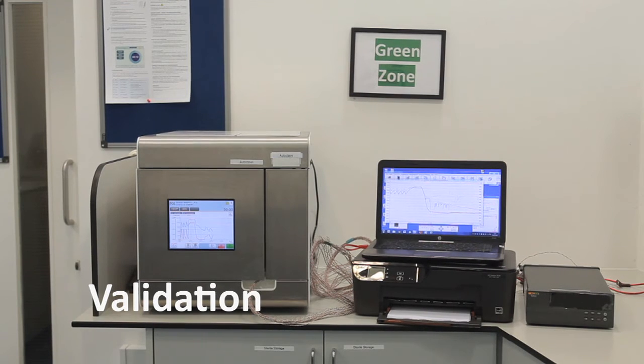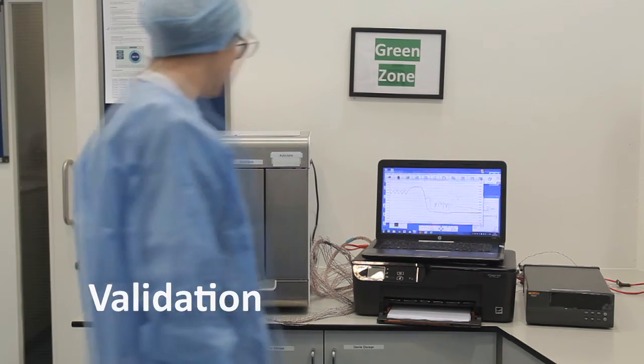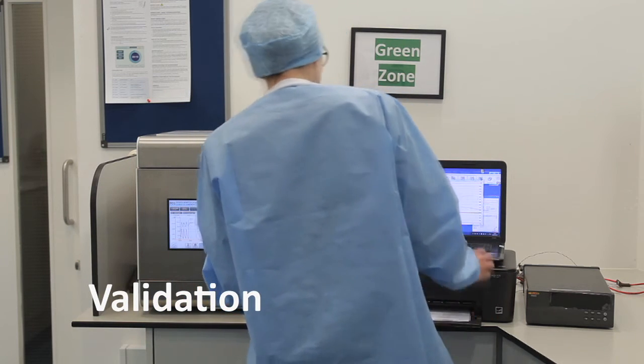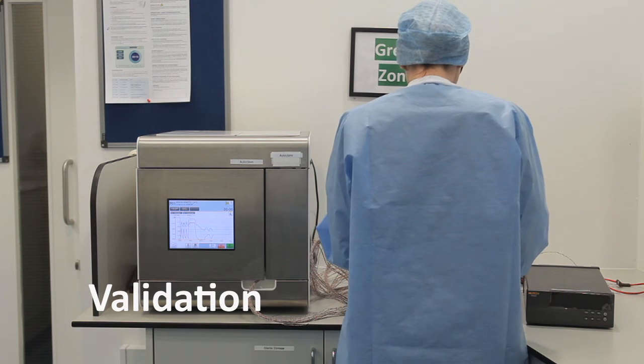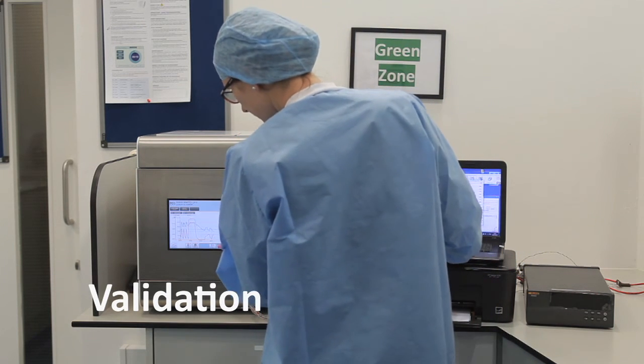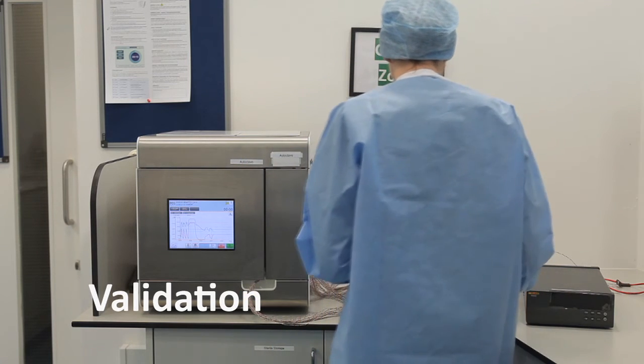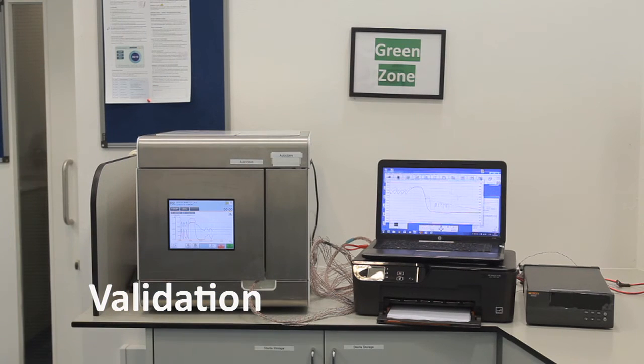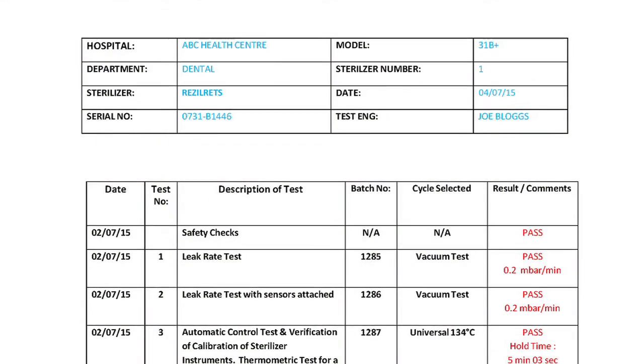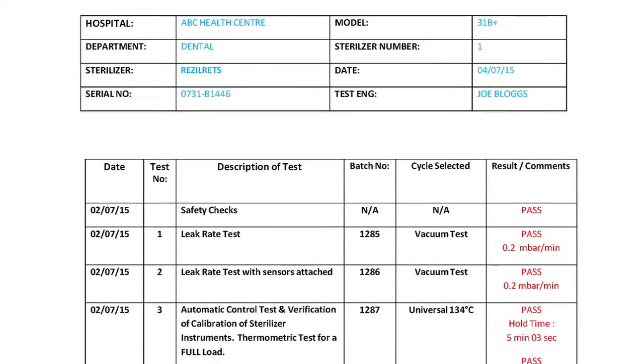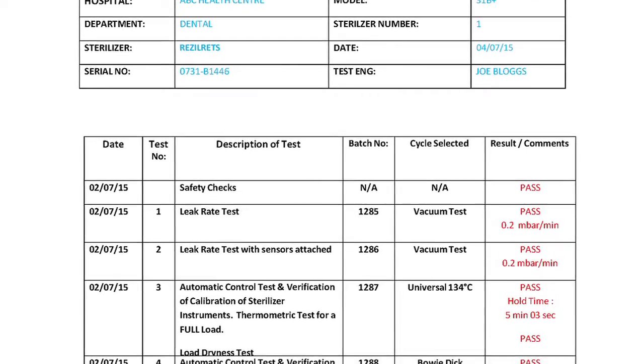Validation is the documented procedure for obtaining, recording and interpreting the results needed to show that a process will consistently yield a product complying with predetermined specifications. The process of validation is to examine all aspects of the decontamination and sterilisation process to determine if they are operating and functioning correctly. An independent engineer test person from an outside organisation is required to service, repair and validate the ultrasonic bath, washer disinfector and autoclave on a regular basis. After each service and validation has taken place, a report is submitted by the company engineer to the customer. It is best practice to check and sign the validation reports prior to storage. It is a legal requirement to maintain and store validation records.